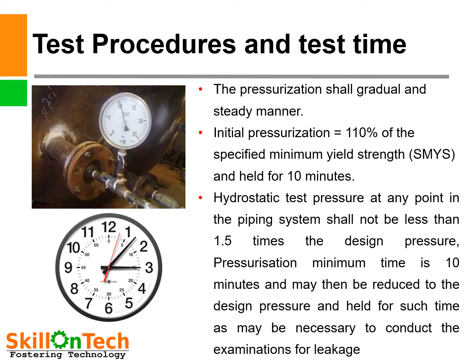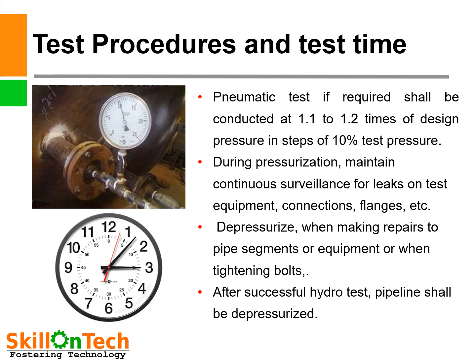After bringing down the test pressure to design pressure, we have to carry out a survey of the entire pipeline and check for joint tightness and leakages if any observed in the piping system. Pneumatic test if required shall be conducted at 1.1 to 1.2 times the design pressure in steps of 10% test pressure. During pressurization, maintain continuous surveillance for leaks on test equipment, connections, and flanges.